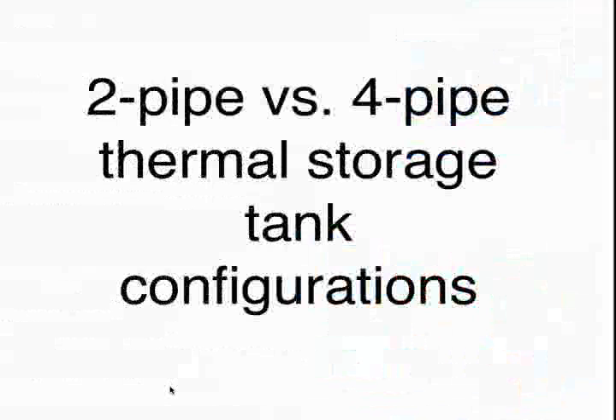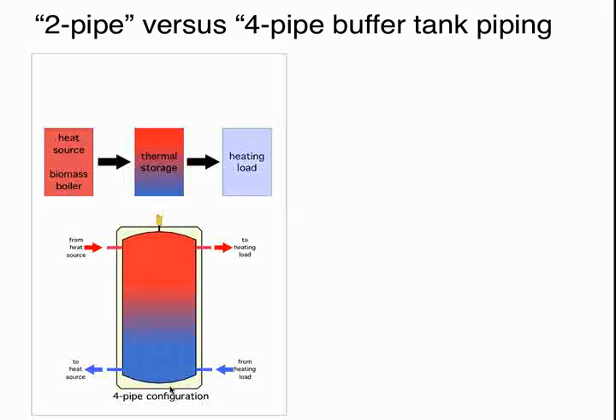Okay, now, next topic. We're going to look at 2 different configurations for thermal storage tanks. And you'll see that there are some minor differences, and many tanks, such as the Thermocon tank from Caleffi, have the connections that allow you to set it up either way. So let's do a comparison, what we call a 2-pipe configuration versus a 4-pipe configuration. The 4-pipe configuration we're looking at here on the left, this is the classic way to set up a thermal storage tank. This has been used in many systems, and it works.